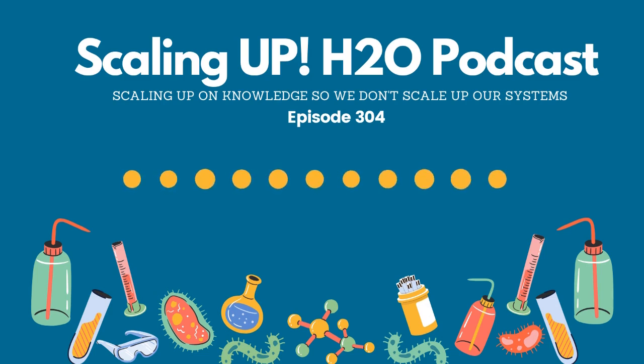So for those of you that just started listening, have no idea what a corrosion coupon is, I hope now you can see that it is the most economical way that you can monitor corrosion rates within the system, so you can proactively adjust your program based on the results of those corrosion coupons. Corrosion coupons come in so many different shapes, sizes, alloys, you name it, you can find a corrosion coupon out there. In fact, I'm looking at a catalog where I get most of my corrosion coupons, and it's almost an inch thick, and all it is is a listing of all the different corrosion coupons that are available out there, and I am sure that that is an abbreviated version.